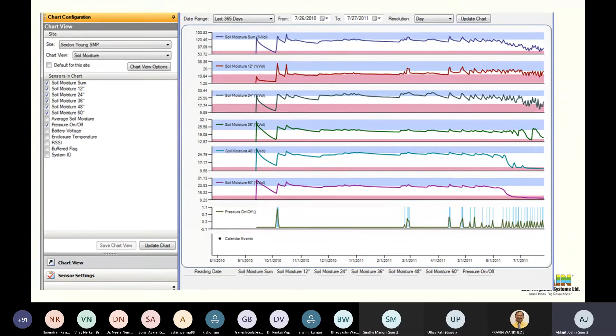Then there is another solution which is called the monitoring solution. Sometimes farmers, as I said, do not want to put expensive automated irrigation controls in their field. Still, he wants to monitor what is happening in the field. So you can put some pressure sensors or flow sensors, because for any irrigation system, there are only two health indicators: the flow and the pressure. So the health of any irrigation system can be analyzed using the trends of pressure and flow. You can put pressure sensors and flow sensors, and analyze whether the pressure is going beyond the given limit, or it is touching the thresholds, something like that. So you can analyze this data, which is called a monitoring solution.